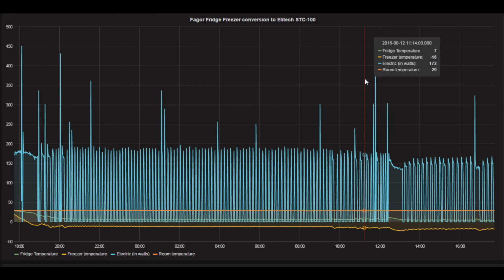I should have placed it a little bit lower, but it doesn't matter with these Elitech thermostats, because you have a calibration mode. So just after 12 o'clock, 1 o'clock, I changed the temperature again. I changed F1 to 0.5 degrees, and I changed the variation to 2 on F2, just to give it a little bit of a cycle break.